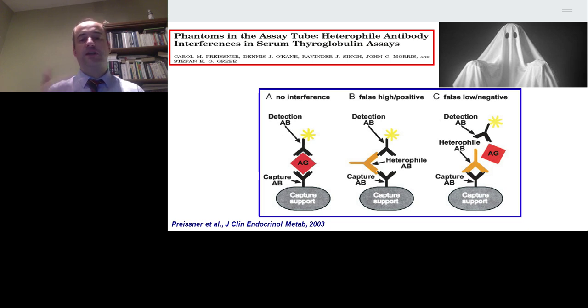And the best practices, where we have also the potential to dilute the sample and see the linearity. If the linearity is not there, you can suspect the interferences. And you have also the option to try to test with another method. Ask one of your partner labs or colleagues, could you test my sample to see if it's something affecting only your method and confirming that you are candidate for interferences.